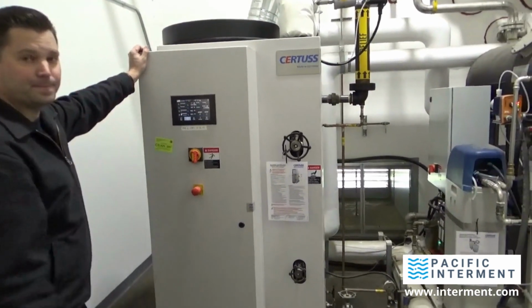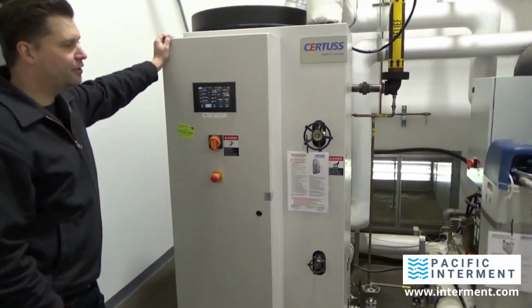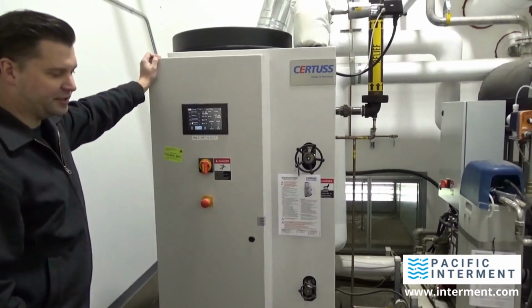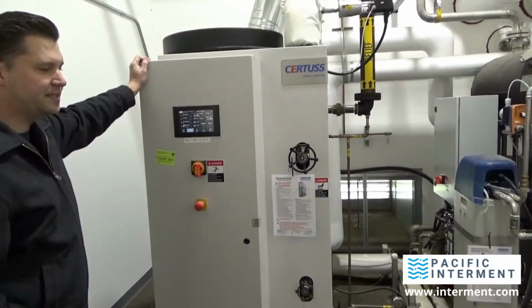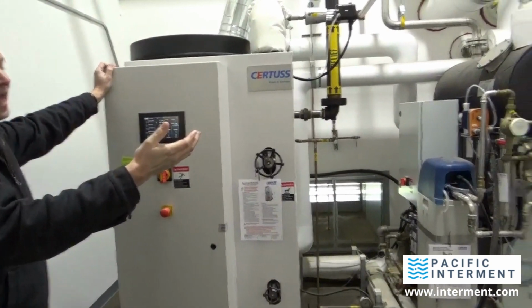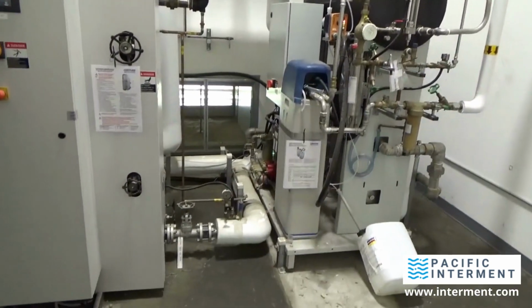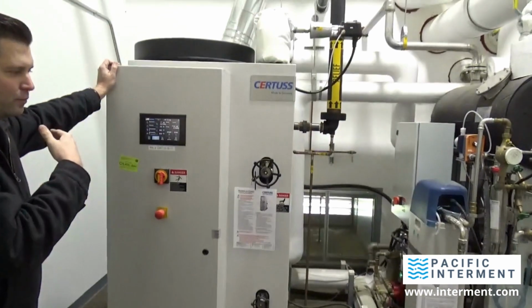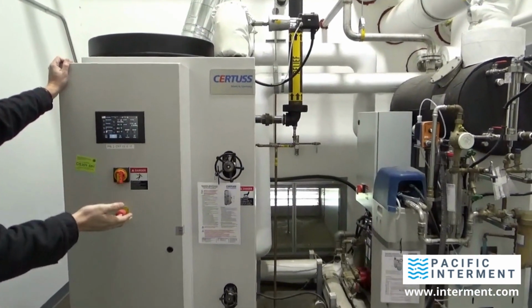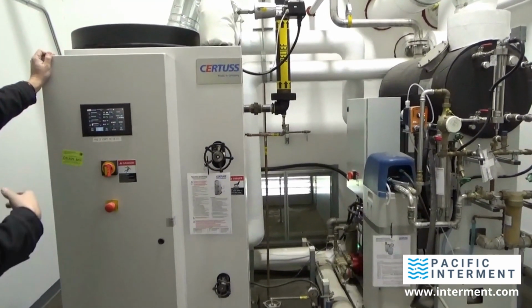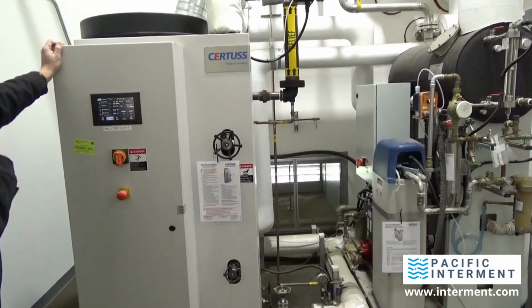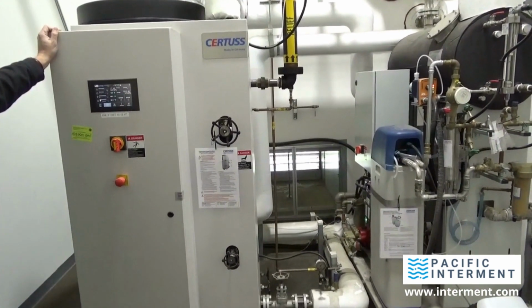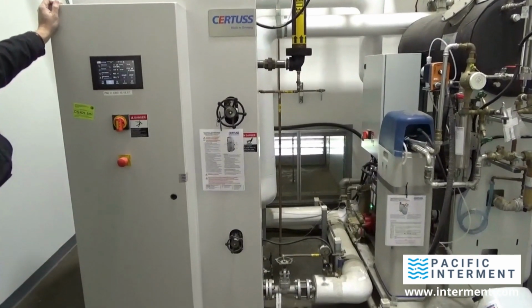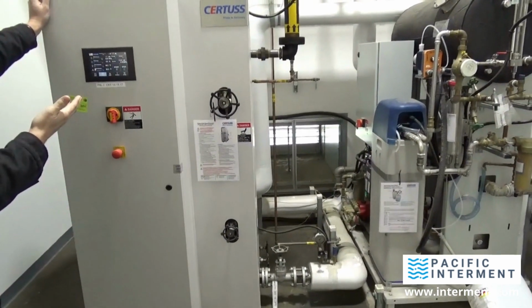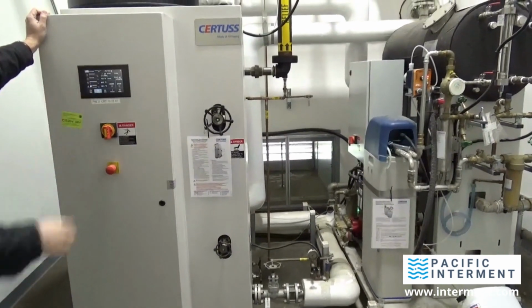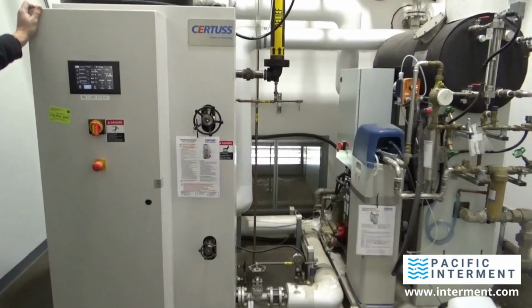Can you explain what a closed loop system is, for somebody who wouldn't know? Essentially it's just super efficient. In a closed loop system, you're capturing the condensate that returns, turning it back into steam, and reintroducing it into the system. So when the condensate comes back in, it might be 260 degrees, making it very efficient to get back up to the 302 degree set point to send back out toward the machine, so there's very little energy loss.